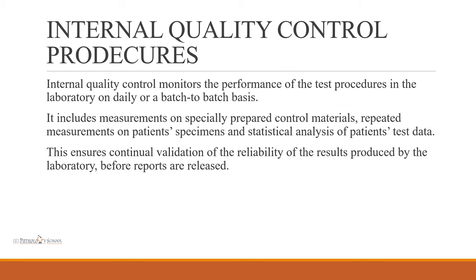Internal quality control procedures: internal quality control monitors the performance of test procedures in the laboratory on a daily or batch-to-batch basis. It includes measurements on specially prepared control materials, repeated measurements on patient specimens, and statistical analysis of patient data. It ensures continual validation of reliability of results produced by the laboratory before reports are released.